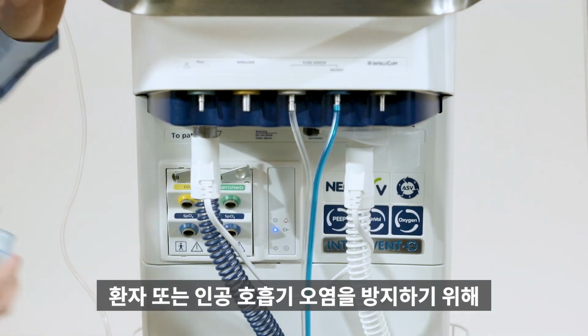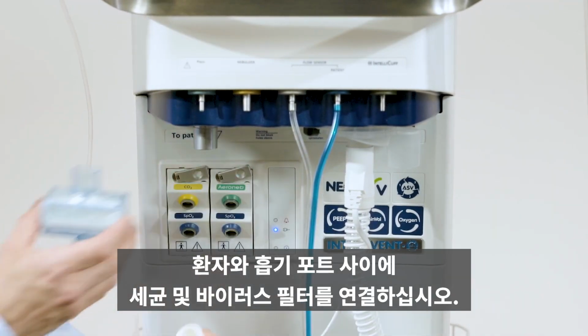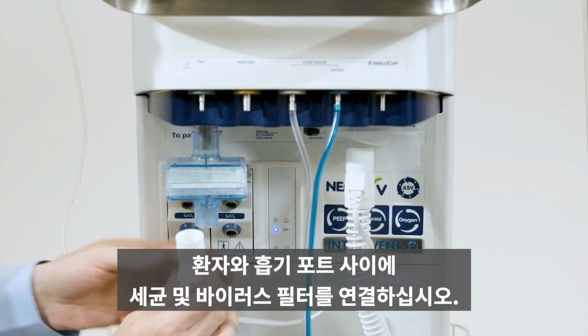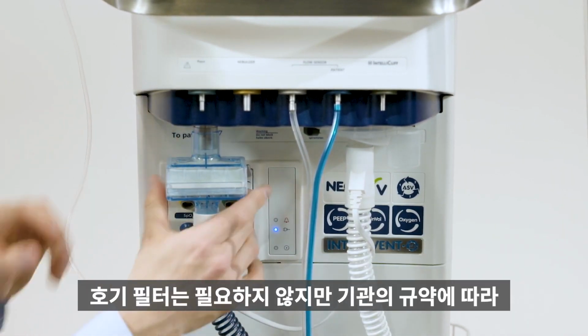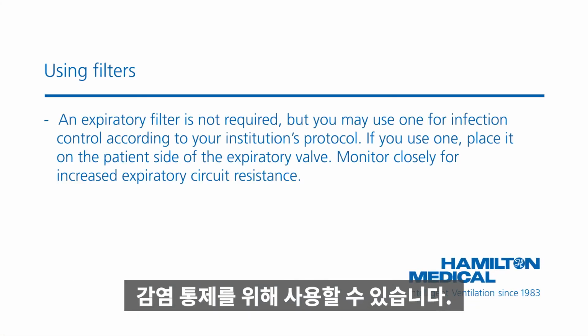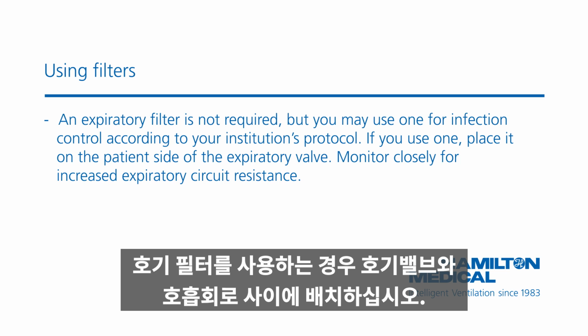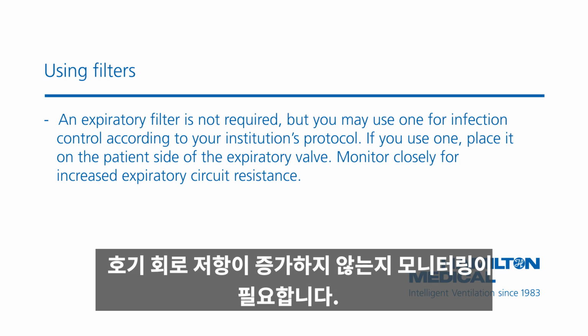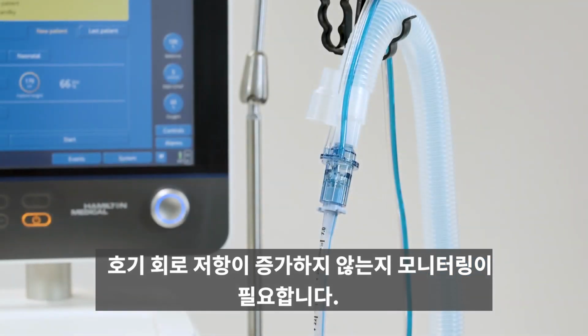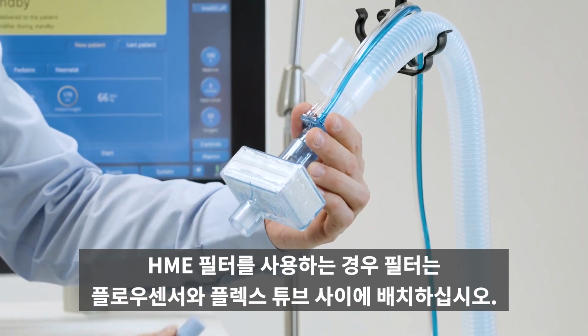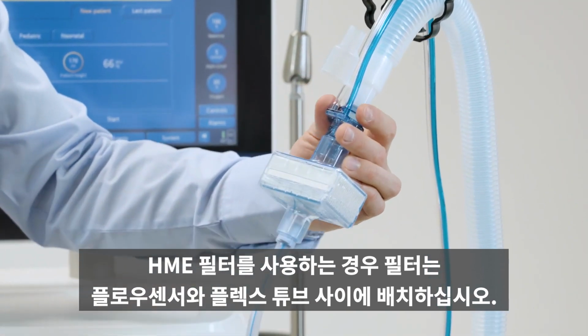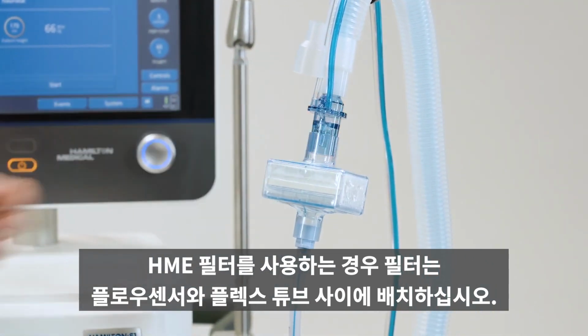To prevent patient or ventilator contamination, connect a bacterial and viral inspiratory filter between the patient and the inspiratory port. An expiratory filter is not required, but you may use one for infection control, according to your institution's protocol. If you use one, place it on the patient side of the expiratory valve. Monitor closely for increased expiratory circuit resistance. If you use a heat and moisture exchange filter, position the filter between the flow sensor and the flex tube, as described in the operator's manual.